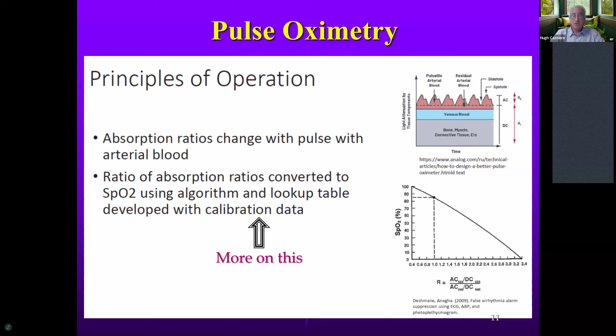Here's how it's made. Again, healthy volunteers breathe gas mixtures with different oxygen levels. There are blood samples taken at each oxygen level. The ratio of light absorption at these two different wavelengths is measured for each sample. This ratio is correlated to the oxygen saturation measurements by these blood gases that you did. The data from many of these healthy volunteers is all averaged to create this calibration curve. This calibration curve is then programmed into the pulse ox, and that's how you get your pulse ox reading.